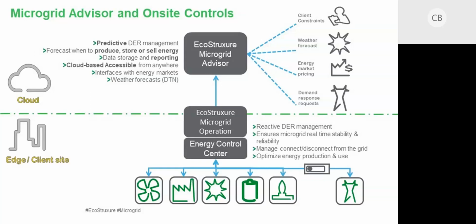Then once we have a model which is supported by artificial intelligence to create this kind of optimized version, we take this information and we download it literally now to the client side where we have the microgrid operation, the EcoStruxure microgrid operation. And this model in the cloud gets updated every 15 minutes for the duration of 3 days. So we download an operational model of our microgrid on site every 15 minutes, which is then good for 3 days. So even if something were to happen and the cloud service is not providing it, we still have an optimized forecasting model, which allows us to operate for the next 3 days.